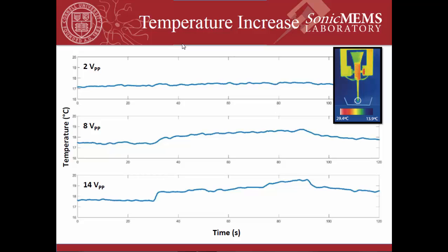So we also measured the temperature of the tip of the transducer when we turned on the transducer at the 3 different voltages. And as you can see, at 2 volts it's very flat. It almost didn't increase at all. But at 8 and 14, you see a slight increase.